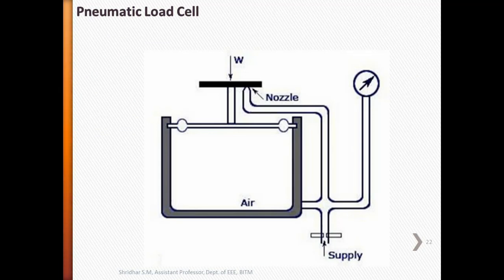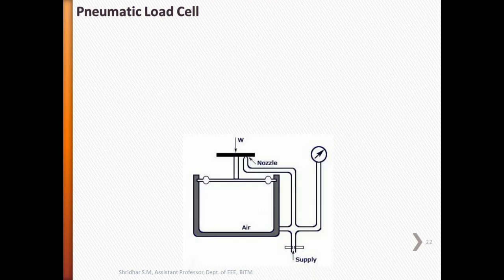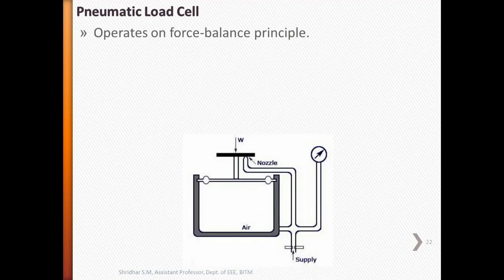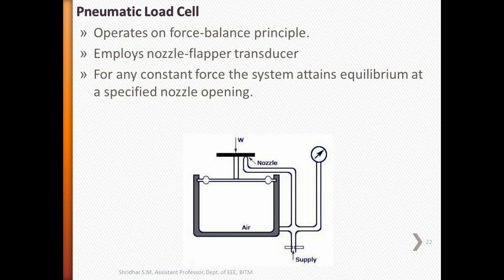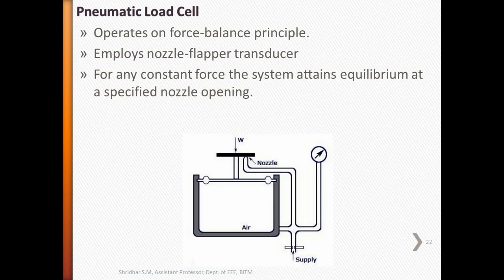Next, we'll discuss pneumatic load cells. These cells operate on the force balance principle. It has a simple construction as shown in the diagram where the physical quantity is supplied through this path, and a weight or force is applied in this direction, which consists of a nozzle-flapper transducer arrangement. For any constant applied force, the system attains equilibrium at a specified nozzle opening. The corresponding pressure is indicated by the meter.